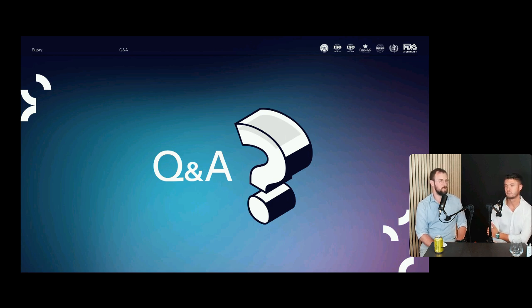Absolutely. And what we're also seeing a lot of auditors starting to focus on is the data analysis part. So if you're using any sort of system to base a GXP decision on, it needs to be validated. And one of the things we see is that if you use something like Excel to analyze your data, you need to validate that Excel sheet. And if you're using a software system, ensure that that system has been validated for the intended use.